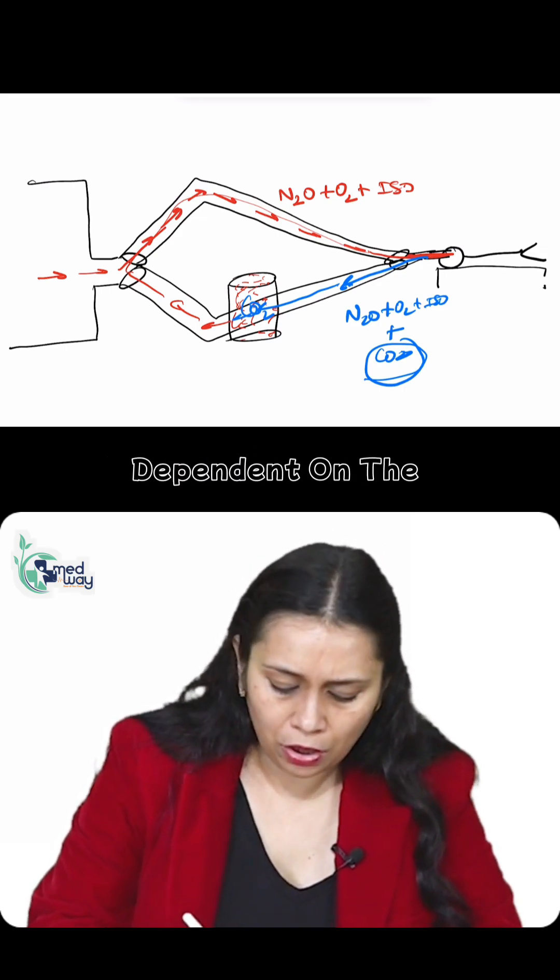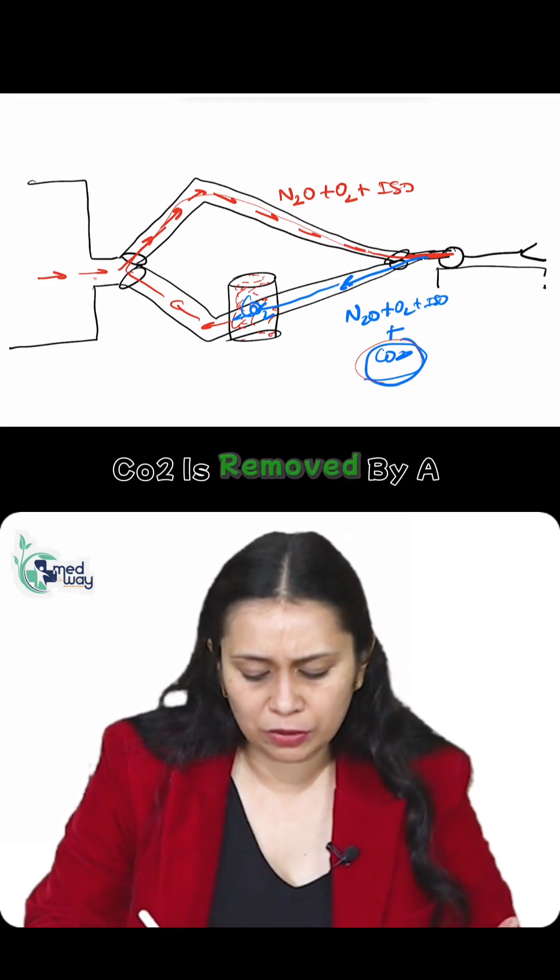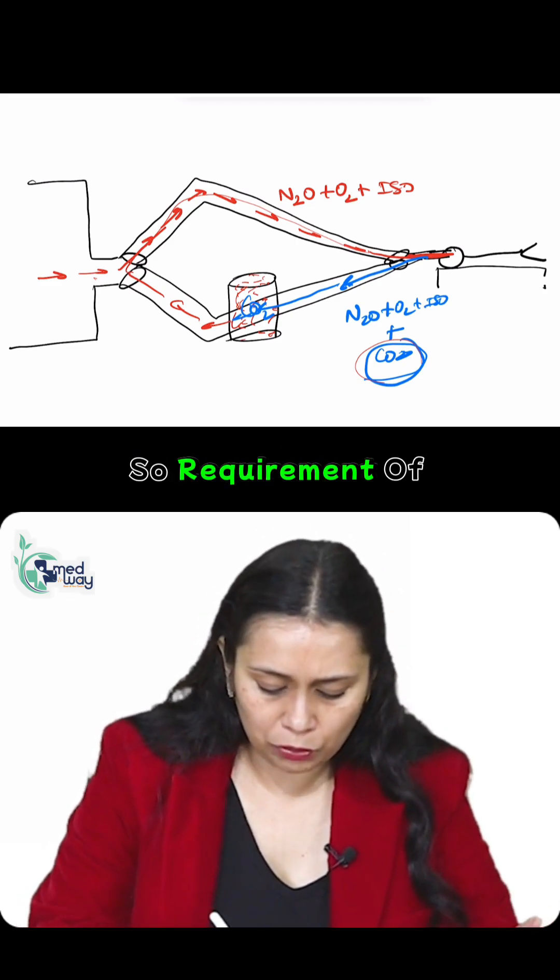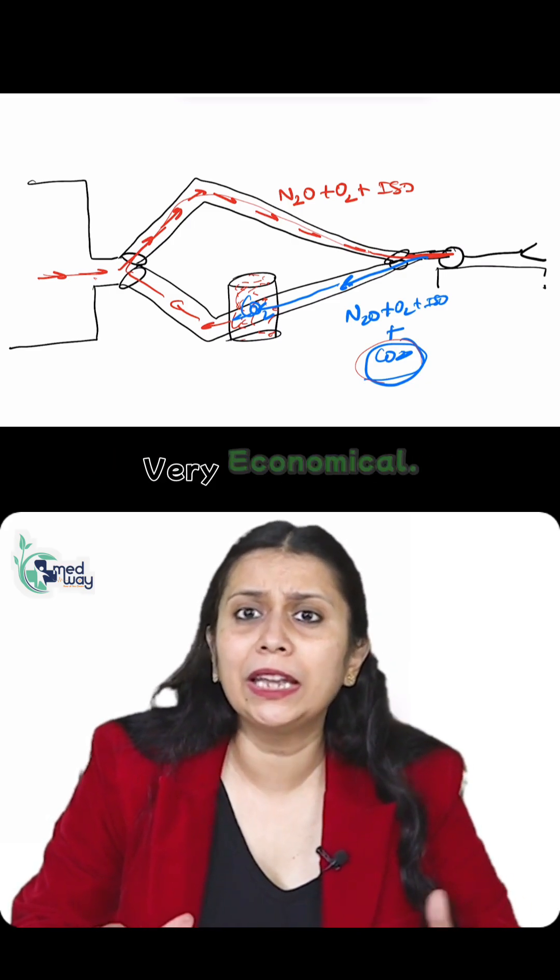We are not dependent on the fresh gas flow for removal of carbon dioxide. CO2 is removed by chemical reaction. So the requirement of fresh gas flow is very minimal, making this circuit very economical.